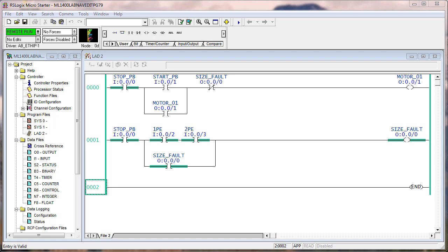Flip the inputs 1 and 2 PE to the opposite position. Did the conveyor restart? No. We never want, if something's stopped because of a fault, you don't want it to automatically start again. That's unexpected motion. Now maybe the operator is expecting it.